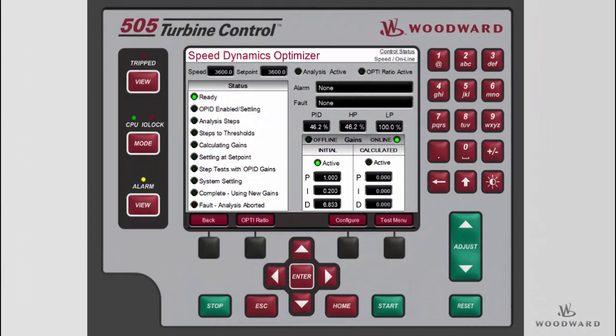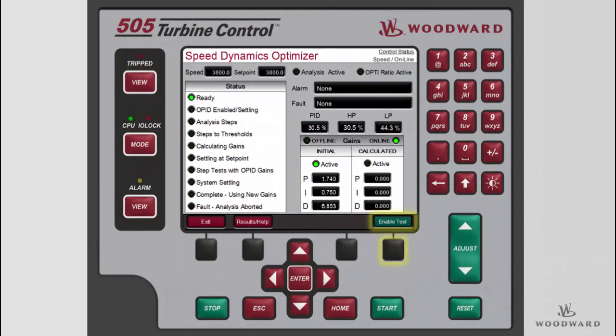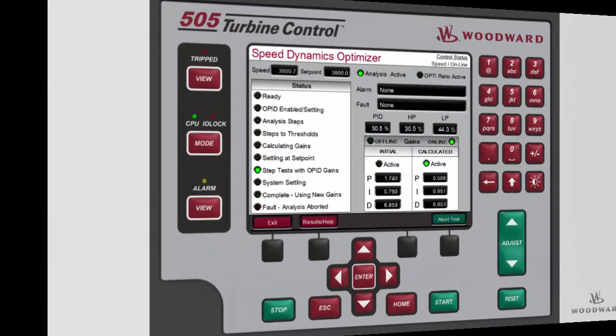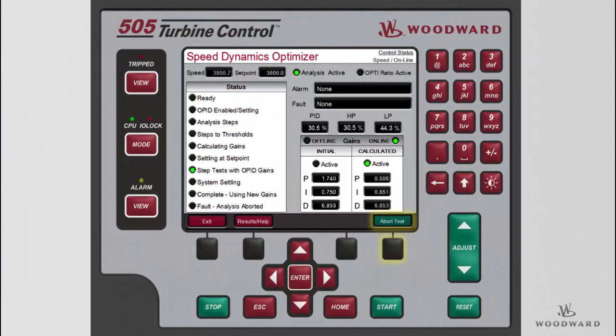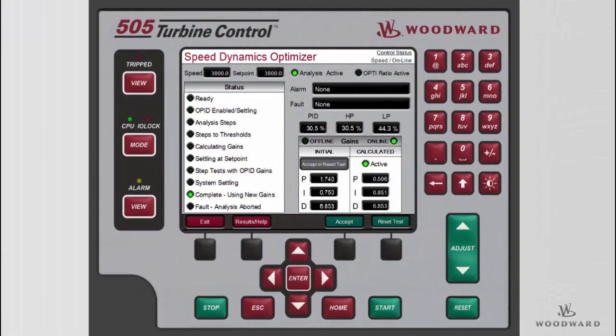When you are ready to run the test, open the test menu from the softkey and press the Enable Test softkey. The test will begin and progress through the steps outlined above. At any point during the test, the test can be aborted by pressing the Abort Test softkey, and the speed PID will immediately control the speed at the initial setpoint using the initial gains. When the test is complete, the Accept softkey becomes available. By pressing the Accept softkey, the calculated gains will overwrite the initial gains and the test will reset using the new gains. To reject the calculated gains, press the Reset Test softkey and the PID will revert back to the initial gains.